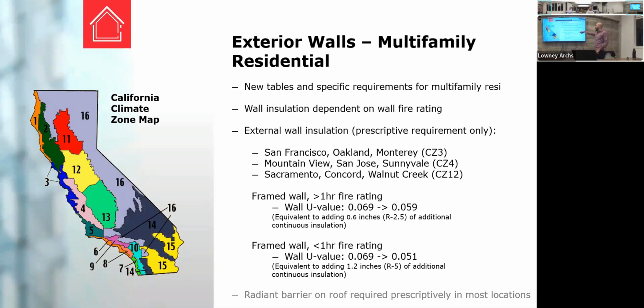Yeah, I think I would talk about the climate zones here. These are just some examples. And for these climate zones, like 3, 4, 12, just like most of where we see the projects, the wall insulation requirement has gone from 0.069 U-value to 0.059. What does that mean? For a metal framed wall, you would have to have a 2 inch thick continuous insulation layer, in addition to that insulation. Now that continuous insulation layer needs to be another 0.6 inches thicker than before to get to this lower U-value. That's an additional R2.5 insulation.